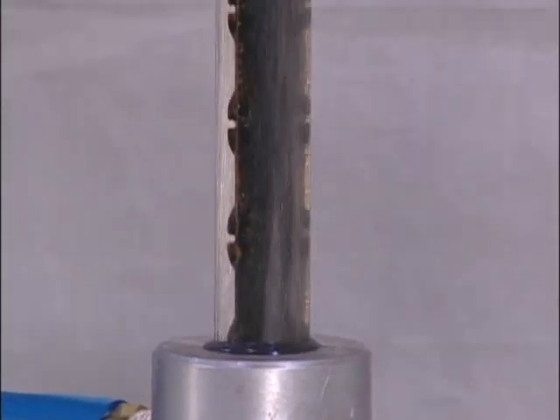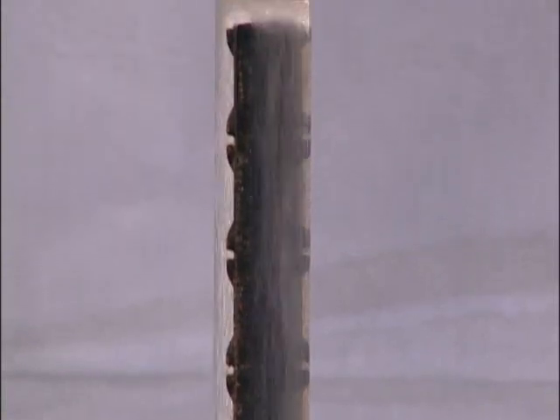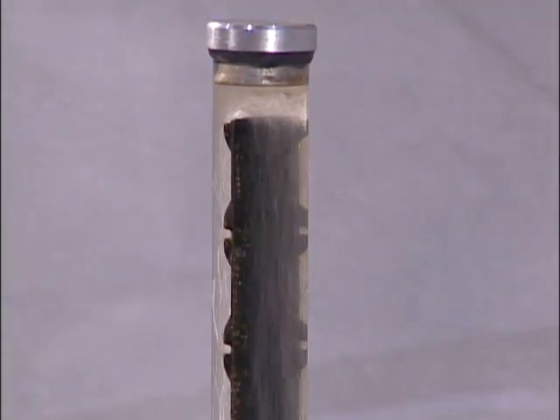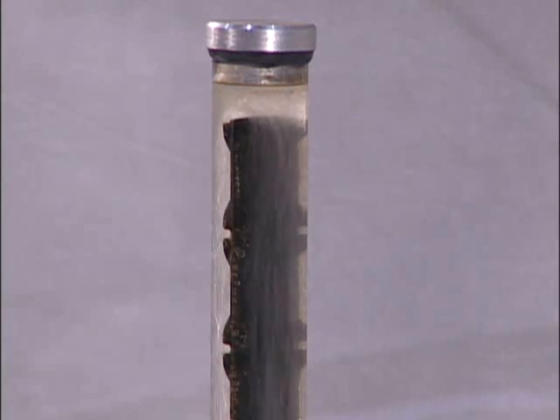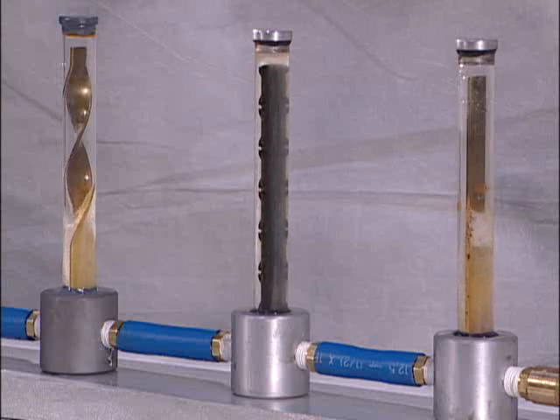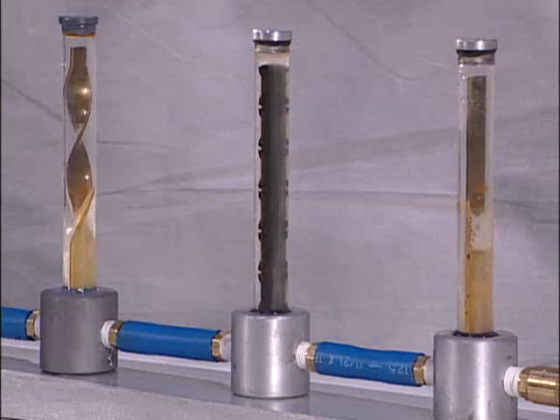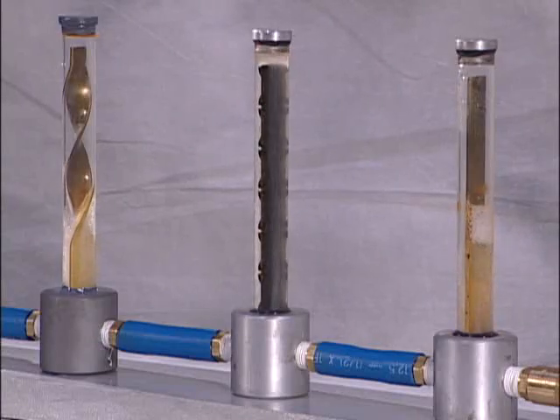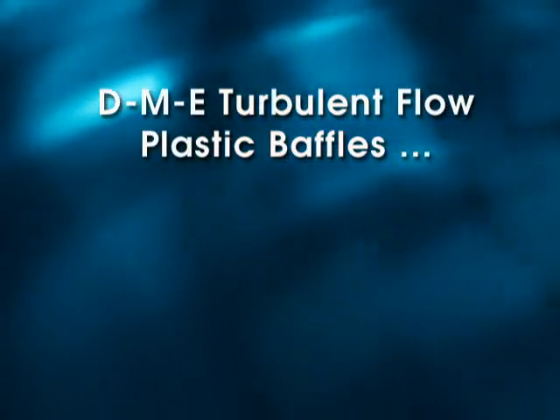Turbulent Flow Plastic Baffles are constructed of a glass-reinforced engineering thermoplastic called polyphthalamide. Polythalamide has a working temperature of 370 degrees for a constant 2,000 hours of heat exposure. Polythalamide is commonly used in automotive radiators because of its ability to withstand the effects of glycol-based coolants under high temperature conditions.